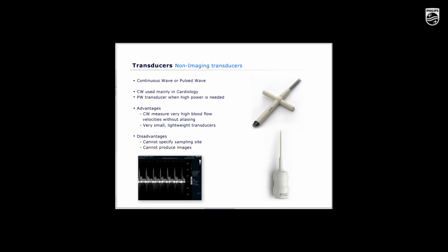Continuous wave, or CW, transducers emit sound continuously. There are two elements within the housing, one that continuously emits sound and one that receives. CW capability can be combined with an imaging probe, however, continuous sound cannot be used for imaging. Pulsed wave, or PW, non-imaging transducers are used when the correct location of the vessel must be identified. Pulsed wave transducers are low-frequency Doppler probes that emit several pulses along the scan line. They provide range detection and allow clinicians to choose specific areas of flow to analyze. Note, other names for these probes are PEDOF, pencil, or static transducers. PW and CW probes are explained in more detail in the upcoming imaging section of this learning.